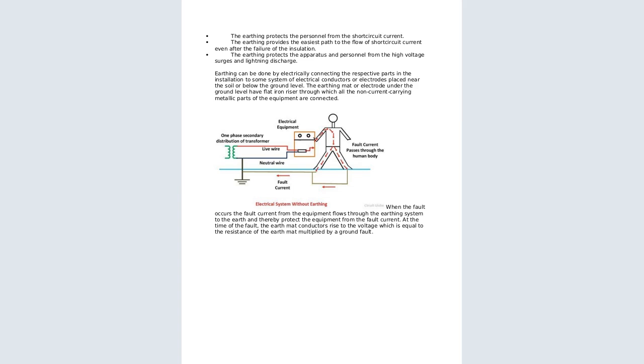So you can now see the electrical system without earthing. When we have an electrical system without earthing, what happens? It will mean that this electrical current will have to go through the person or a human body. Here, from the secondary distribution transformer, you can see this is our live wire coming from the transformer, and this is the neutral wire. So if there is no earthing, this is an electrical equipment, and this person has just touched this electrical equipment, meaning this current is going to discharge through this person and goes to the ground. And the moment it passes through the human body, the person has been electrocuted and might even die on the spot.